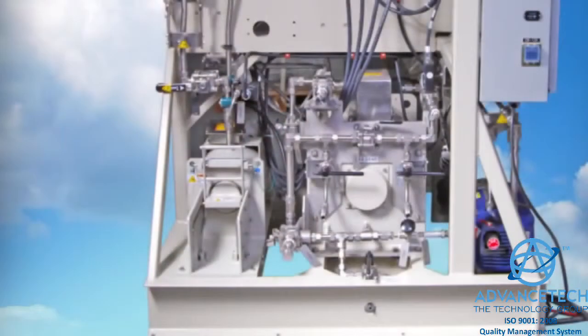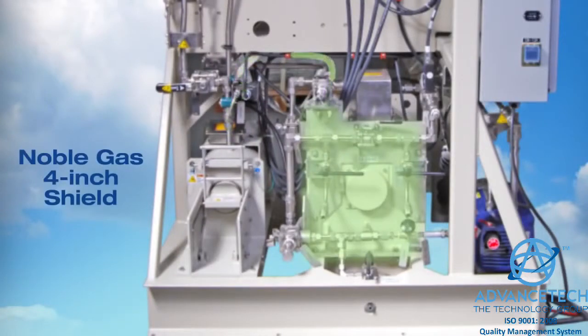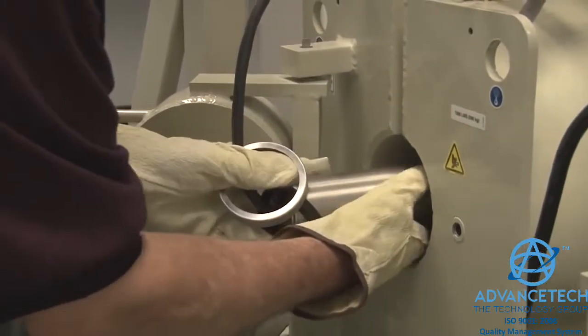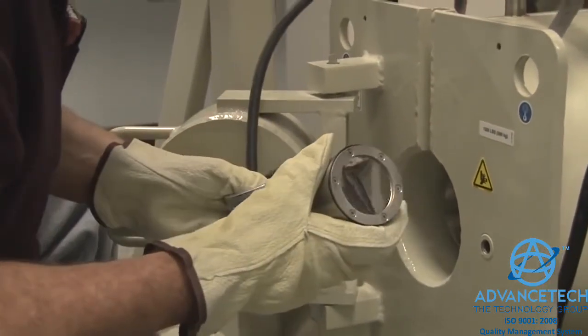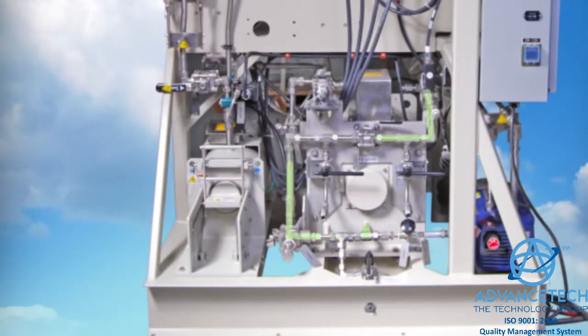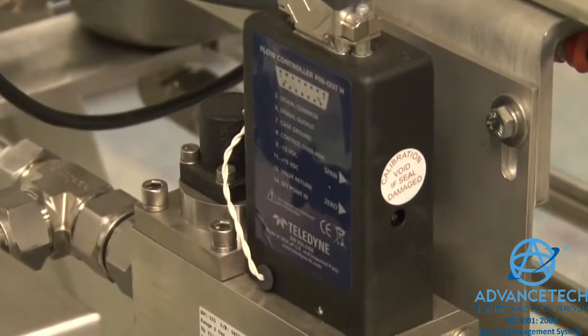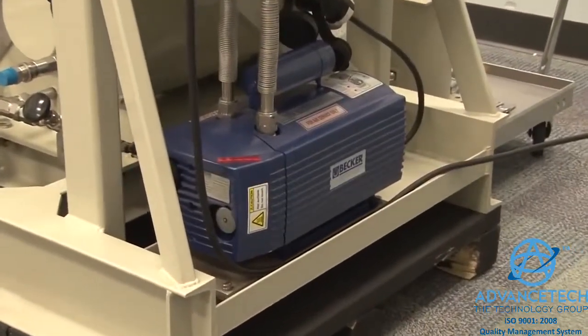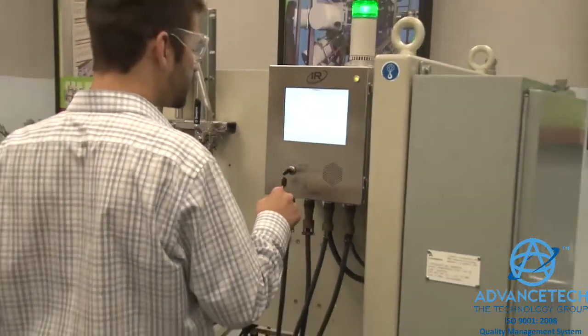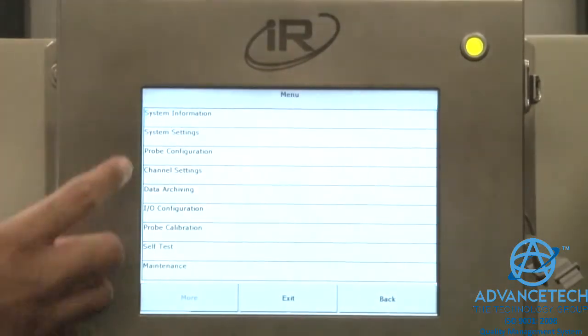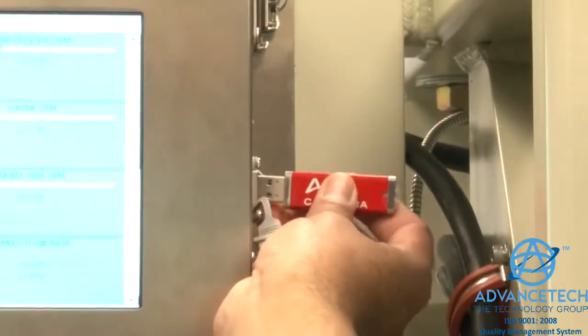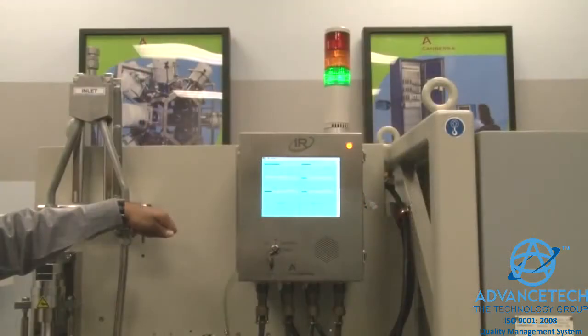The flow exits the particulate and iodine shield and then enters the 4-inch shield for noble gas, which houses a plastic scintillation detector in front of a 3-liter Marinelli chamber. Next, the flow exits through the noble gas chamber and passes through the flow controller and then through a pump to the outlet. The IR7040 intelligent rate meter powers and controls system detectors, displays and records data, and provides visual and audible alarm indication with dry relay contacts.